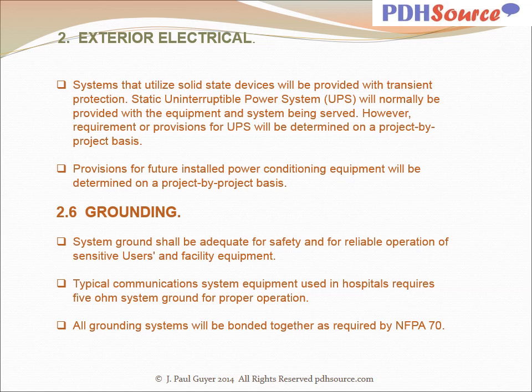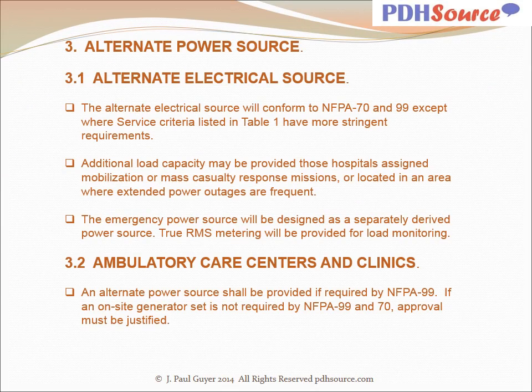With regard to grounding, system ground shall be adequate for safety and for reliable operation of sensitive users and facility equipment. Typical communication system equipment used in hospitals requires 5-ohm system ground for proper operation. All grounding systems will be bonded together as required by NFPA 70. With regard to an alternate power source, the alternate electrical source will conform to NFPA 70 and 99 except where service criteria listed in Table 1 have more stringent requirements.